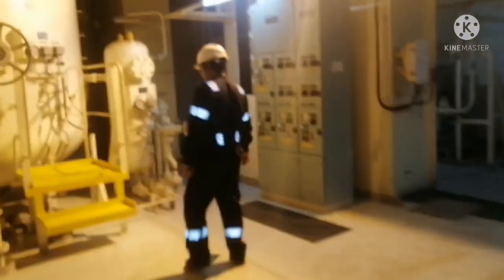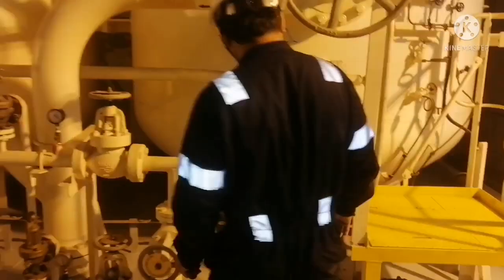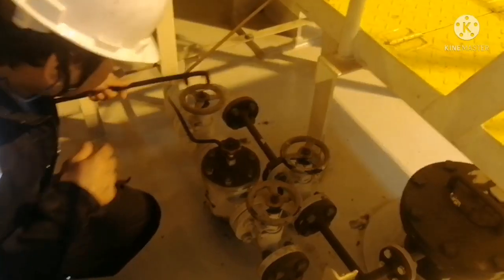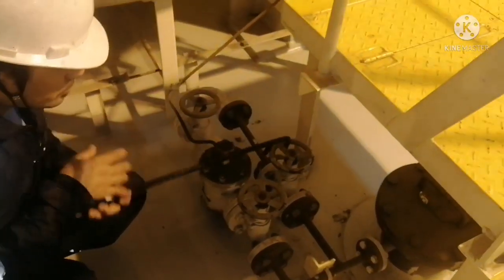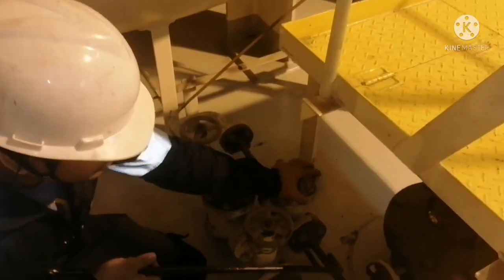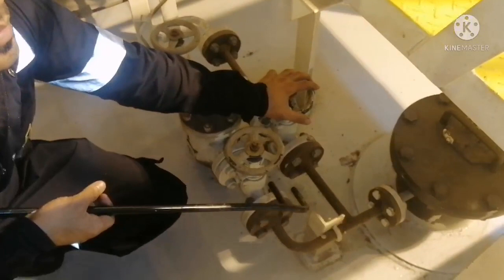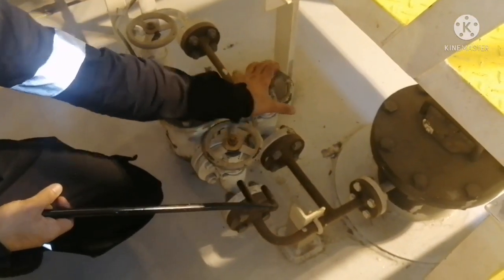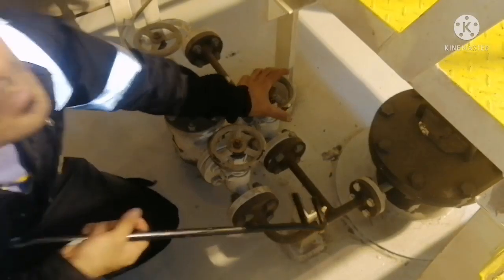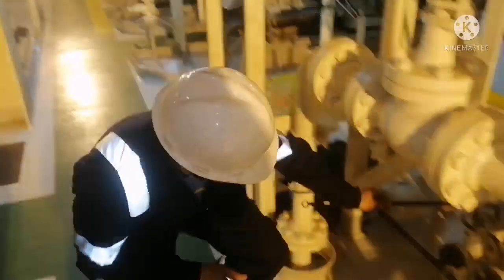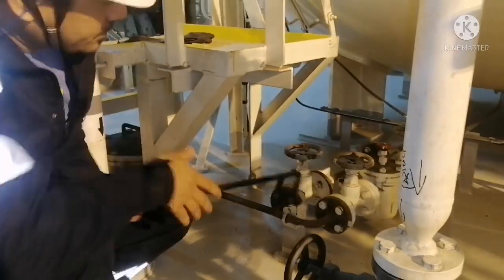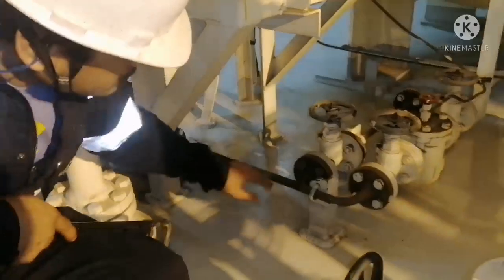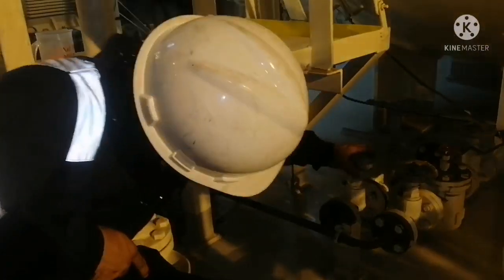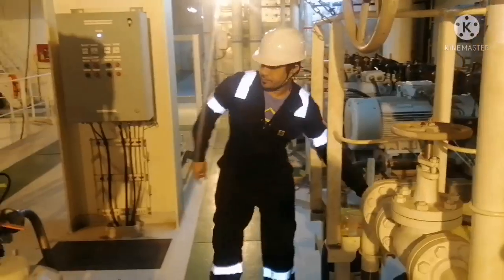Next, we go to the air bottle side. Generally, whenever you go for a round, you have to drain the air bottle so that whatever moisture is inside the air bottle will be drained off. We have two air bottles in this ship, so you have to drain both of them. When you drain it, you can see the water coming out through the hopper, which is your drain area where the water comes out.